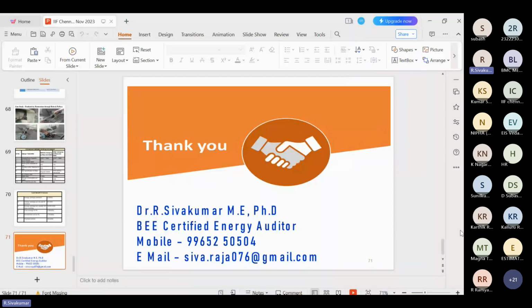See, normally for the auxiliary loads, for 433 voltage, there is a solution with the OLTC, on-load tap changer. But for furnace applications, whether small capacity or higher capacity, the OLTC is not placed in any furnaces, because the furnace secondary voltage is different, 575 volts. Yes, sir.